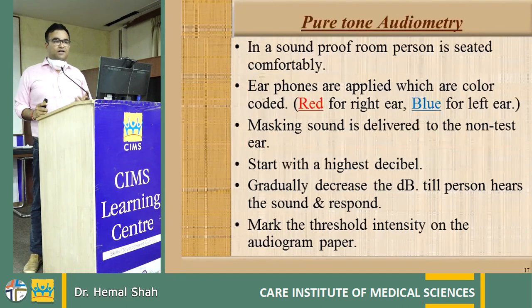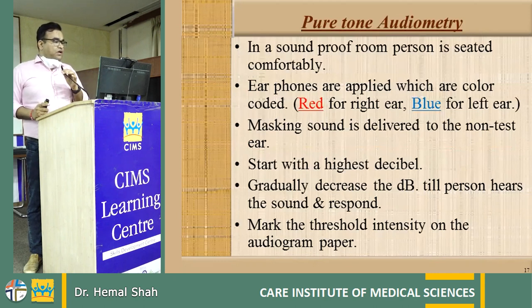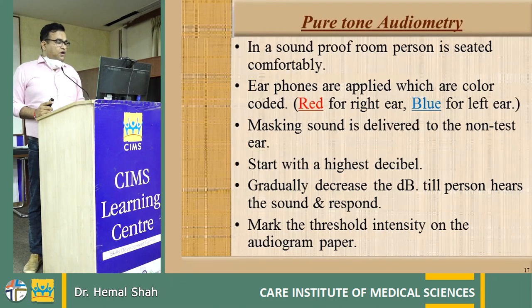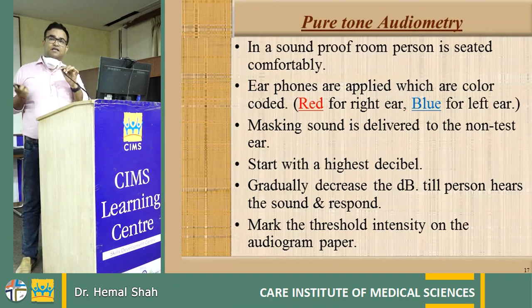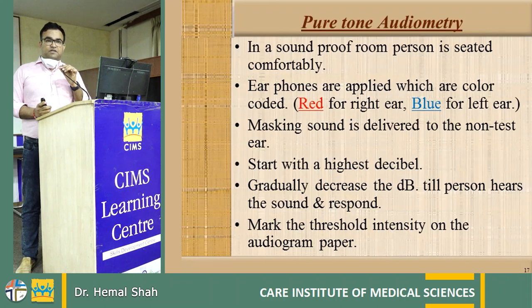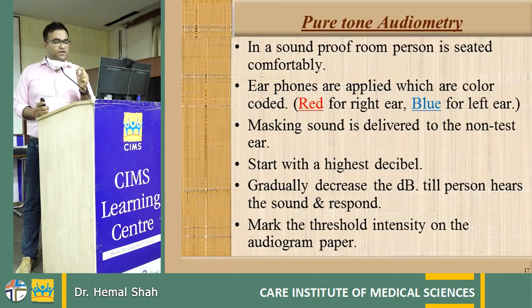How is pure tone audiometry performed? It should be done in a soundproof room. The person is seated comfortably, and earphones — color-coded red for right and blue for left — are applied. Masking sound is delivered to the non-test ear. Start with high-pitch, high-decibel intensity and gradually lower the decibel intensity to determine the person's threshold for each particular frequency, continuing until the person hears the sound and responds.